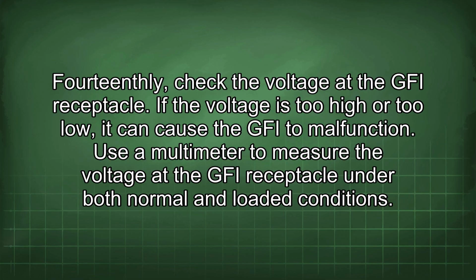14thly, check the voltage at the GFI receptacle. If the voltage is too high or too low, it can cause the GFI to malfunction. Use a multimeter to measure the voltage at the GFI receptacle under both normal and loaded conditions.